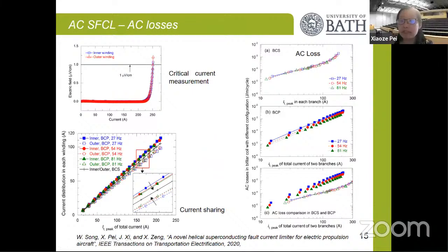So when we measure the superconducting fault current limiter, the first thing we need to measure is the critical current of the superconducting tape, because this is a very important aspect. We need to make sure the critical current is higher than the normal operating current, so it maintains the superconducting state during normal operation. And 1 microvolt per centimeter is the normally used criterion, and based on our design, the critical current is very similar to the critical current of the tape. Which means during the winding process, there is no degradation.